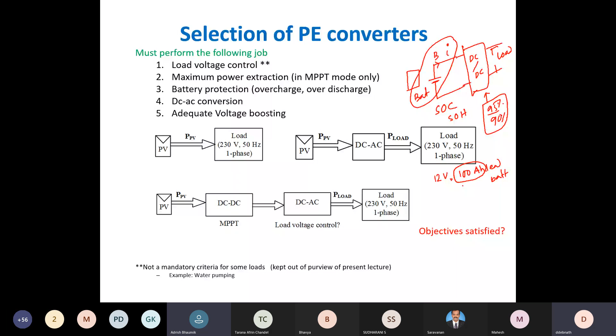There's a catch for lead acid batteries specifically. This is generally defined on a 20-hour basis. So if you draw 5 amperes from the battery, it can sustain that for 20 hours. Most people think if you draw 10 amperes, it'll last 10 hours, and if you draw 1 ampere, it'll last 100 hours. That data is wrong. In most standard definitions, this is actually based on 20 hours.